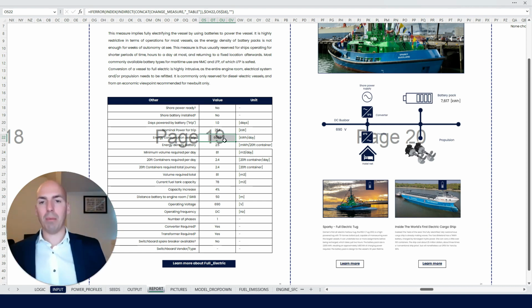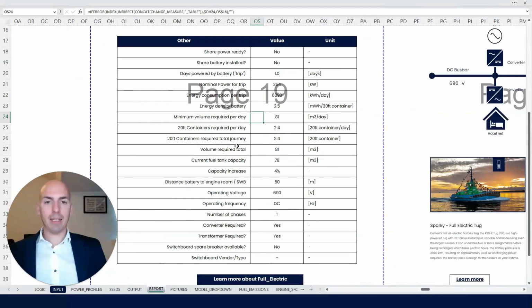But maybe the battery supplier can provide better assumptions there and decrease cost. Like I said, we've assumed very energy dense battery packs. I'd say 2 megawatt hours per 10 feet container is max, so 2.5 megawatt hours per 20 feet container is doable. We could put the battery pack inside the vessel, but we still need a lot of fire protection depending on the cell chemistry. So 2.5 megawatt hours per 20 feet container is a good estimate for the entire system, including fire suppression and cooling systems, since you can combine single 20 feet containers.